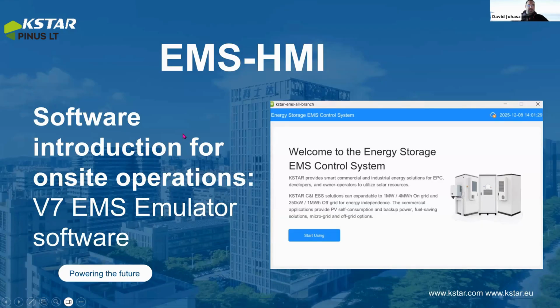So we can set a lot of things here, which is the diesel generator startup SOC, for example, the off-grid depth of discharge, for example. There are many things to adjust here. And here we can set the running mode. We have 4 running modes supported by KSTAR. One is the manual control, mostly for third-party device controlling of the system and testing the system. Next is the self-consumption, and we have the time of use and the peak shifting. I will show all 4 later in a standalone sheet.